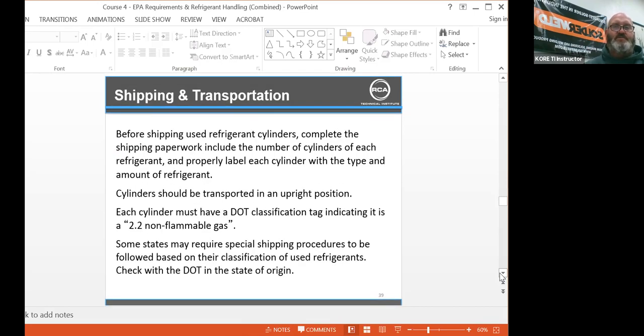Before shipping used refrigerant cylinders, complete the shipping paperwork, include the number of cylinders of each refrigerant, and properly label each cylinder with the type and amount of refrigerant. Cylinders should be transported in an upright position. Each cylinder must have a DOT classification tag indicating it is a 2.2 non-flammable gas. Some states may require special shipping procedures to be followed based on their classification of used refrigerants, so check with the DOT in the state of origin.